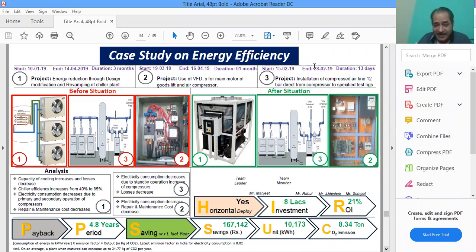So we need to analyze our systems and understand what we can do for better energy management. Similarly, for project number 3, our compressed air requirements needed two different pressures for two different sets of equipment in the plant - one around 6 kgs and another requiring 12 kgs. We did away with running one compressor system up to 12 kgs for equipment that didn't need it.